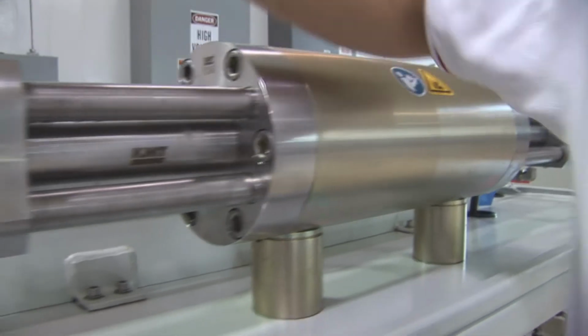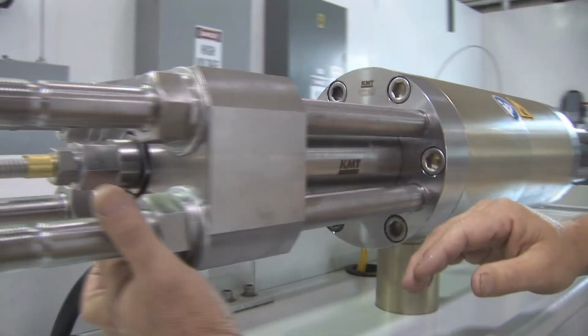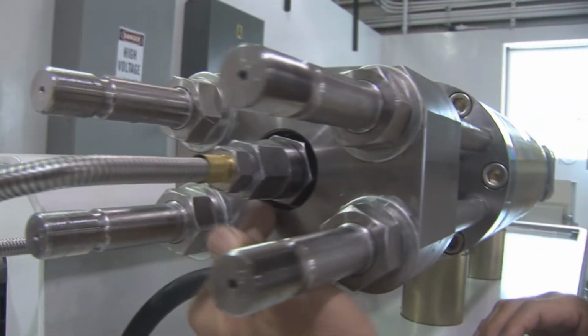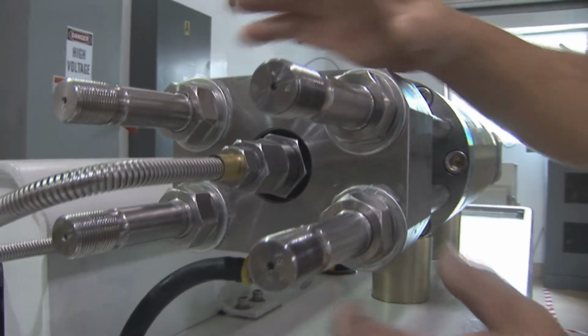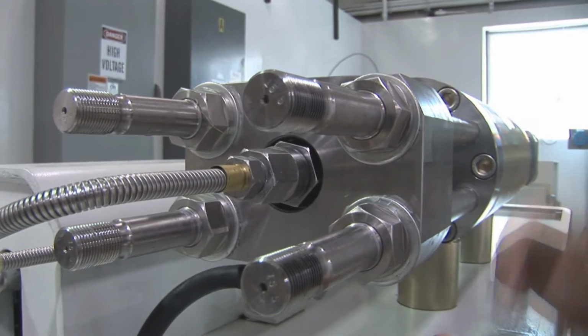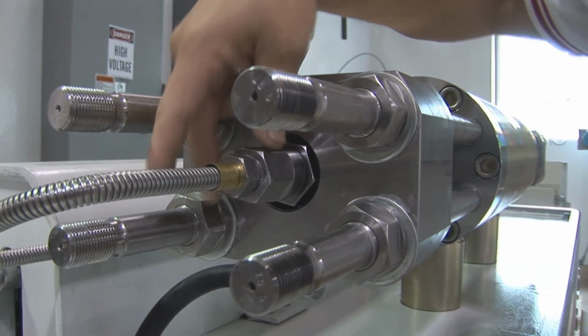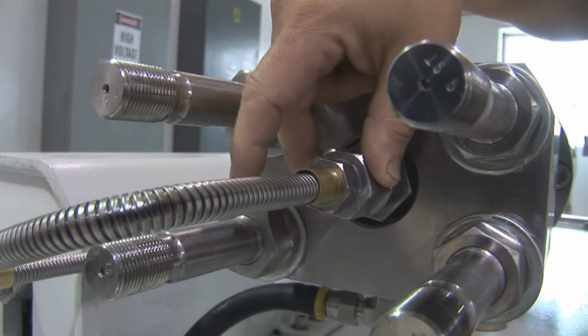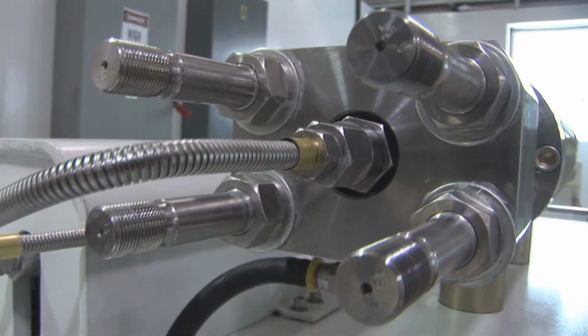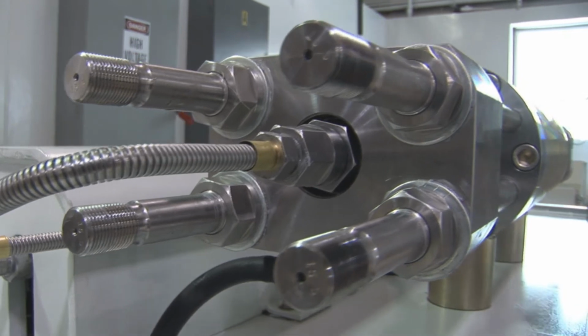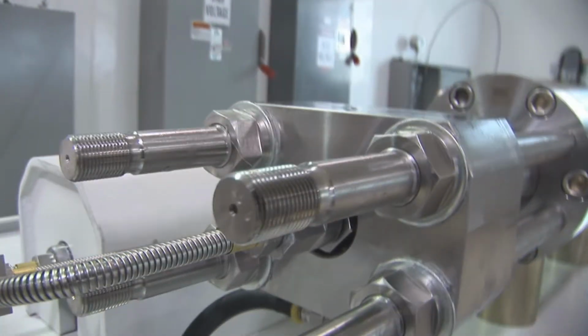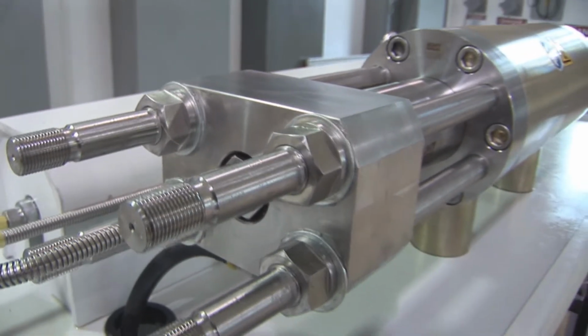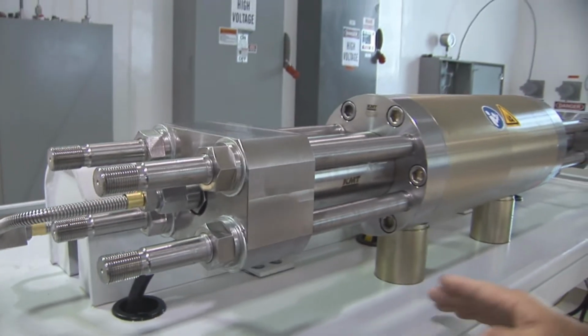If water is leaking out the head nut over here, around this area, there's a good chance that maybe we didn't get these torqued properly, or we may not have the seal head nut tight enough. We could have water dripping out of there also. These things need to be torqued in an even pattern. We'll get into that a little bit later on in the video, I think.